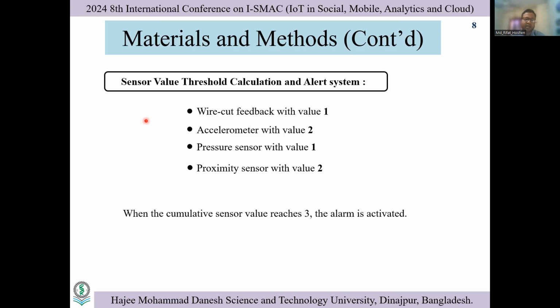For the pressure sensor, we used a force sensitive resistor. This sensor also has a value of 1 and detects if any bolts securing the transformer are being loosened or not. For the proximity sensor, we assigned a value of 2. It detects if someone is too close or wants to move the transformer or the control box. The system only triggers when the cumulative value reaches 3 or more. This threshold-based approach helps to reduce false alarms caused by minor disturbances or environmental factors.